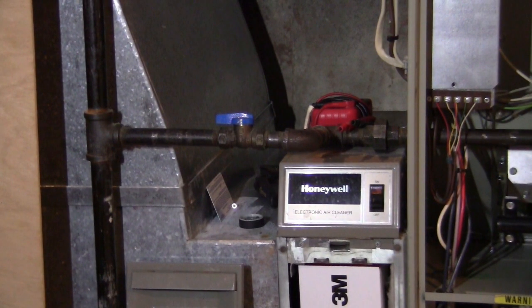First of all, this is a gas furnace, and this part is where the gas comes from the gas provider and comes in here. There is a valve. This is a manual valve. We can use it to turn on and shut off the gas from the outside to the unit. With this valve turned on and off, we can service the unit without the gas leaking.